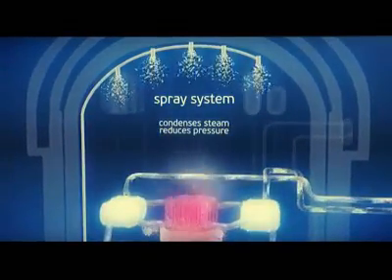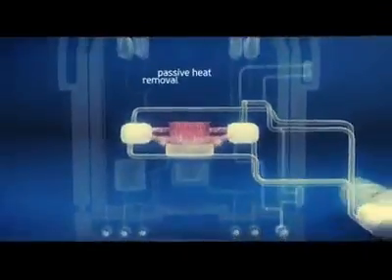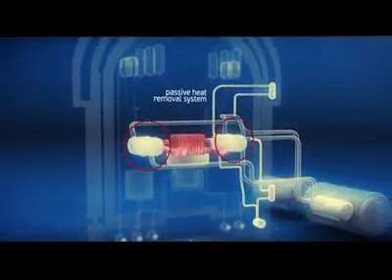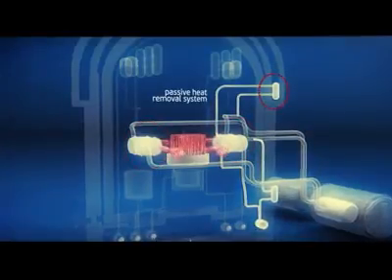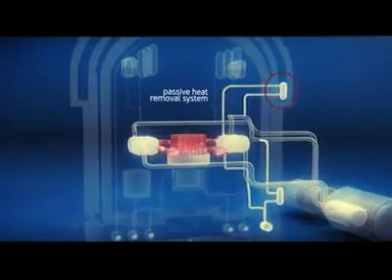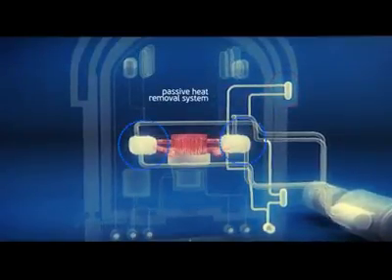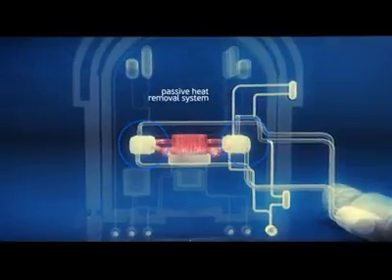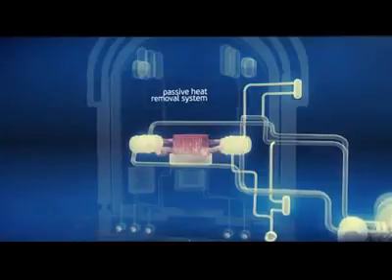Rise of pressure and temperature inside the containment is prevented by spray systems which condense steam incoming from the non-integral reactor. The passive system ensures heat removal from the reactor core through the steam generator — it takes away steam and sends it to the heat exchanger installed outside the reactor hall. Being cooled by outdoor air, the steam condenses and, as water, returns to the steam generator. Thereat, the steam generator is cooled and in turn cools down the primary water and, correspondingly, the core.